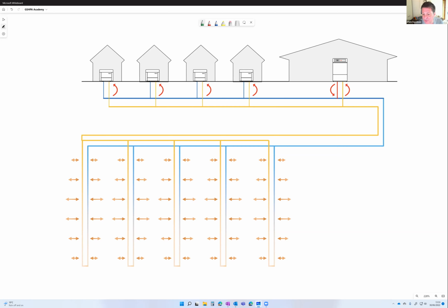So it can act in both directions, either pushing heat out into the ground, or sucking heat out of the ground, and it can do so dynamically. It can also do so without being controlled, because these ground source heat networks are designed, not controlled. So these heat pumps can just turn on and off to suit themselves, and they can either reject heat into that heat network, or suck heat back out, or do it in a mix mode.